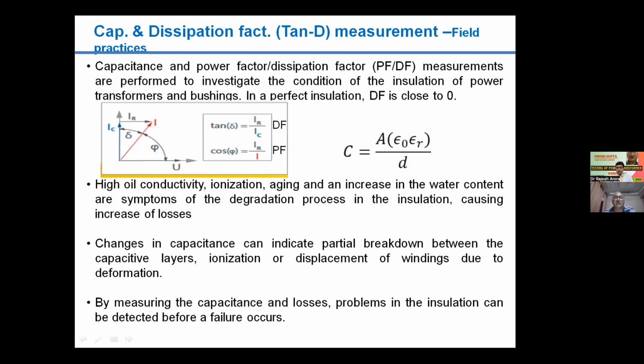By measuring the capacitance and losses, problems in the insulation can be detected. Not only in insulation, even if something went wrong during transportation, that may also be indicated through these tests. Means variation in tan delta may happen in that case also.